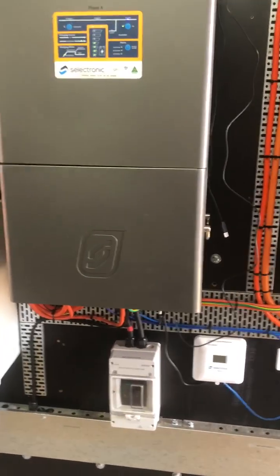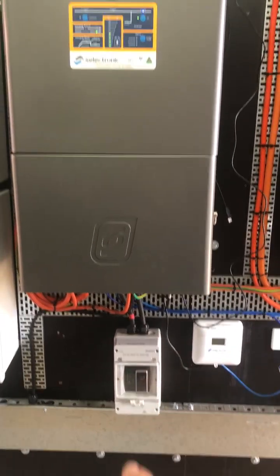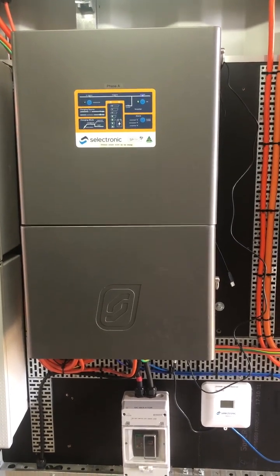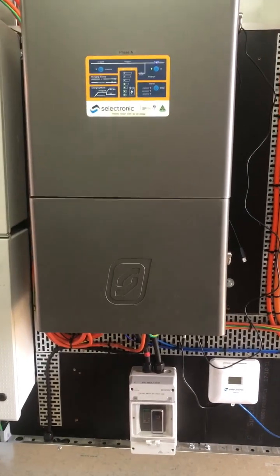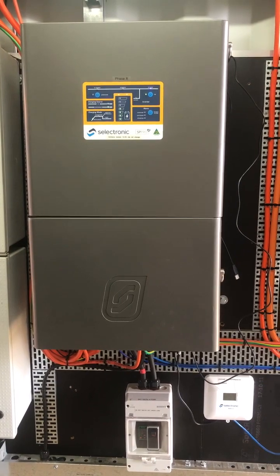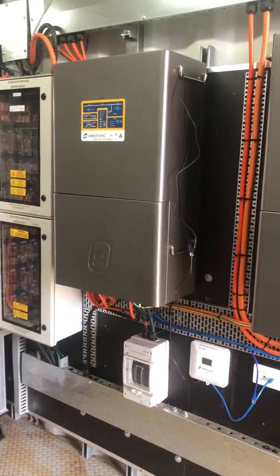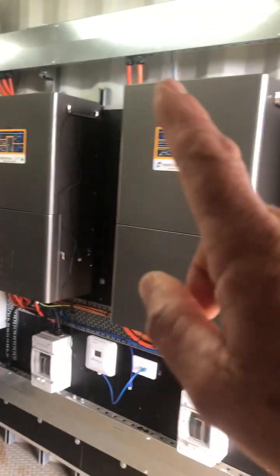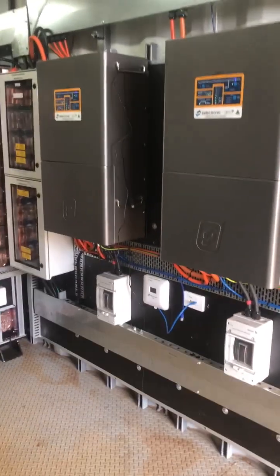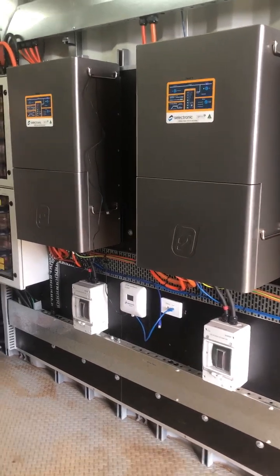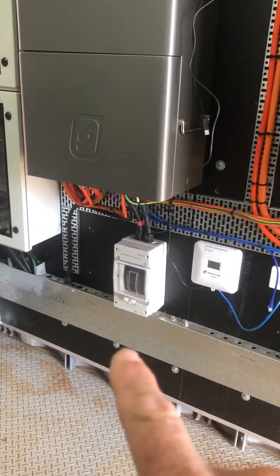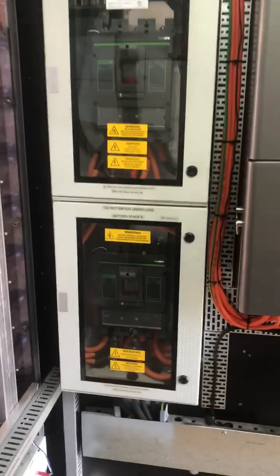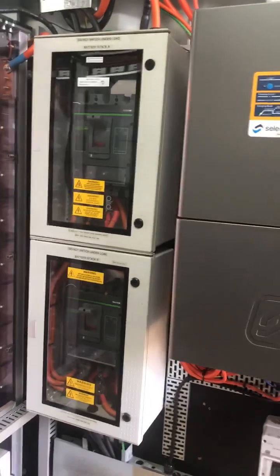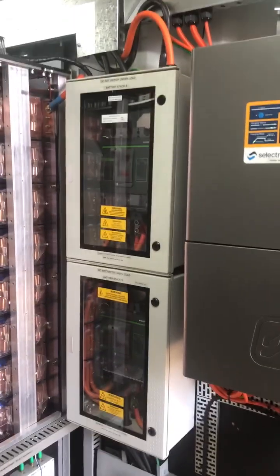Underneath each inverter you'll notice we've got what's called a DC isolator. These inverters are converting the DC volts from the battery into AC volts, alternating current, in this case 240 volts at 50 hertz. Each inverter is 240 volts, but between them, remember, with three phase, it'll be 415 volts. Each inverter has its own DC isolator, and those DC isolators are rated at 250 amps. Then the cables come down from the DC isolator, along, and into these fairly significantly sized isolators. They're quite big. Each one of those is rated at 630 amps. However, we've got them wound back to 400 amps each.